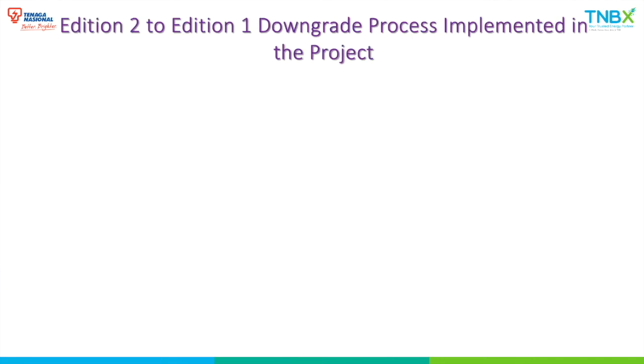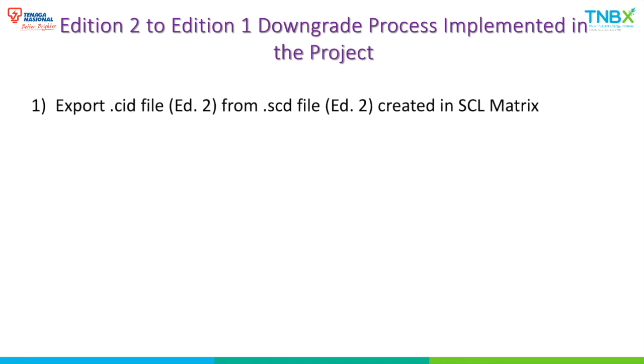Although we tried to follow the first methodology highlighted earlier, unfortunately for the Edition 1 IED in the project we had to devise our own method to downgrade the SCL files to ensure import into the Edition 1 ICT was successful. So our process is a non-standard one: first we export the CID file from the SCD file created in the SCT tool.